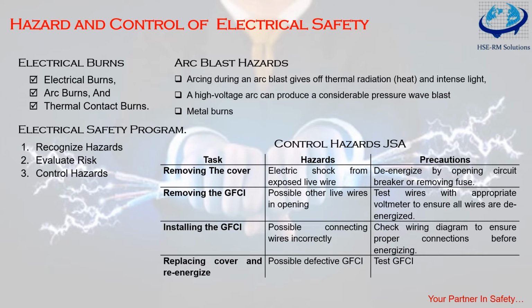Now, what are the arc blast hazards? There are three primary hazards associated with arc blast. Arcing due to arc blast gives off thermal radiation, that is heat, and intense light, which can cause burns. Several factors affect the degree of the injury, including skin color, area of skin exposed, and the type of clothing that you are wearing. Proper clothing, work distance, and overcurrent protection can reduce the risk of such burns.